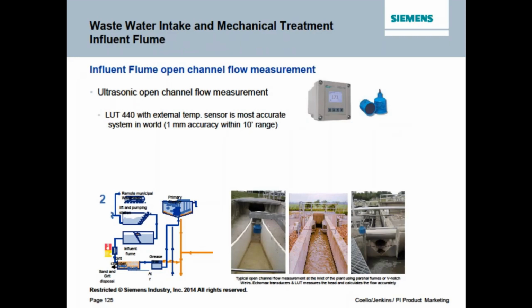Haven't talked much about open channels so far, but to touch on this real quickly, there's 3 big reasons that ultrasonic make more sense than radar for open channel. First off, the majority of ultrasonics nowadays are going to have open channel flow tables built into the transmitter itself. So you can go in and choose the type of flume or weir that you have, and it will convert the level measurement to a flow rate for you based on the change in head height just before your flume or your weir. But ultrasonic is faster in response, has a quicker response time than radar. And in many cases with these open channels, you're constantly changing that head height as your flow rate changes. So you want something that responds very rapidly.